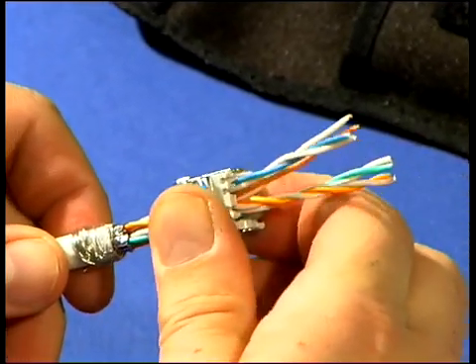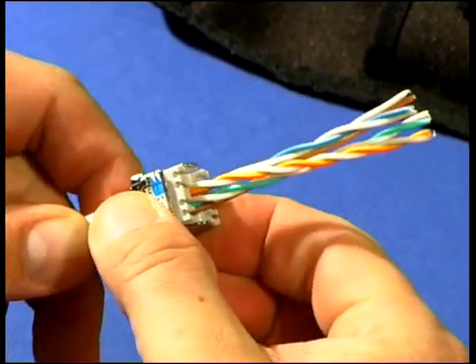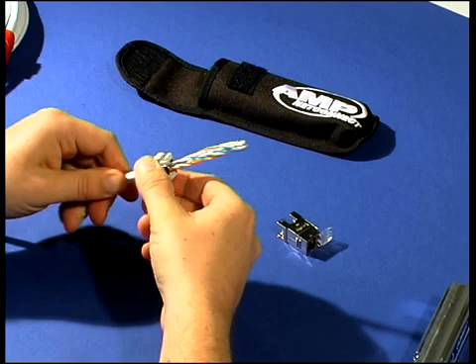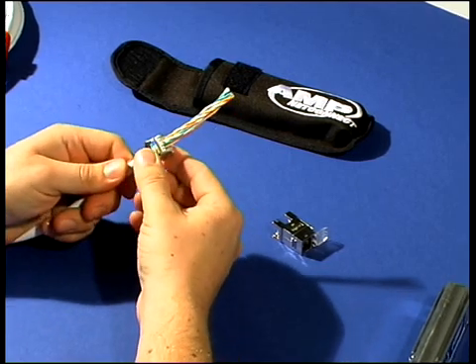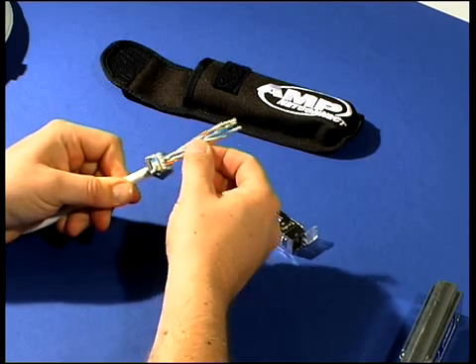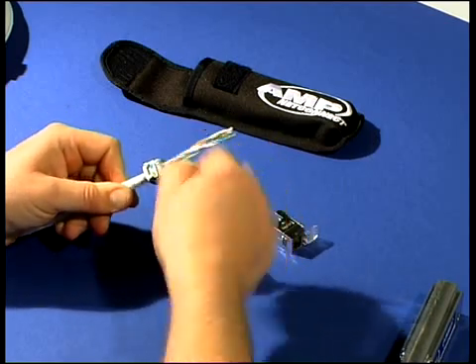Put the backside of the AMP-TWIST connector onto the cable and turn it so that two of the four pairs match the color coding of the wiring diagram. The shield clamp must grab the cable sheath, not the pair foils.